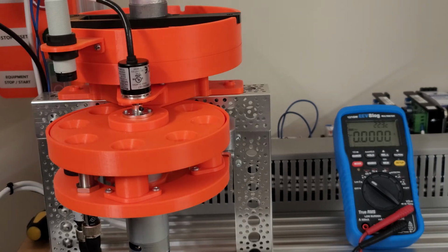And I did a little test on the computer before I came over here to validate that the integer value that we're throwing out to the output card is relatively the correct midpoint of 32,767.